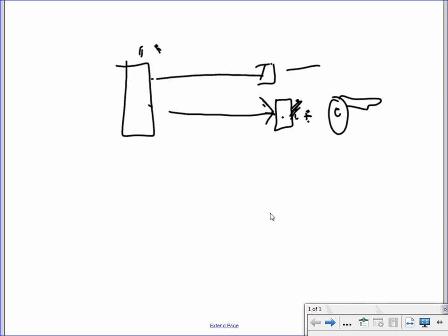I'm not sure if they typically give a normally closed dry contact in the control system of the air handling unit. If it's a normally closed contact and you energize the coil that drives that contact, you just open that little contact, and it shuts down the air handling unit.